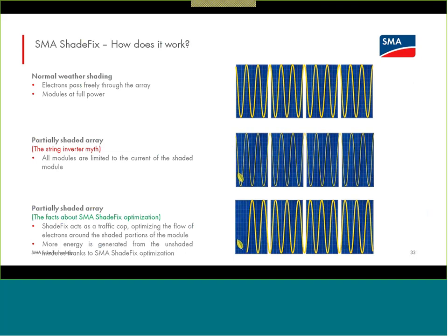And so for Shade Fix, there's a sweep function that allows the inverter simply to determine which of these points produces more power. It does that very efficiently and is not always in operation, but is always checking periodically to make sure the system, even in conditions of partial shade, and this could be snow impacts, whatever, is working each string, or really for the CORE1, each input channel, at the best possible power point. So it's managing all 6 of those inputs independently.